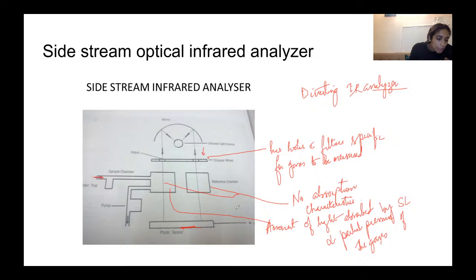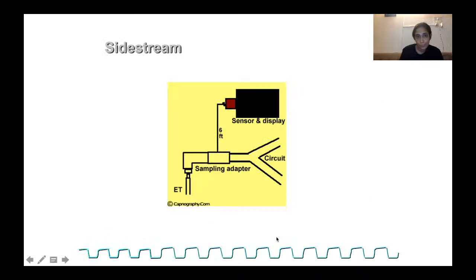Okay. Then the changing light levels on the photosensor produce changes. There is electrical current passing through this photosensor. So this change in the light produces changes in the electrical current running through it, producing your waveform on the display. So this is how your side stream infrared analyzer will work.